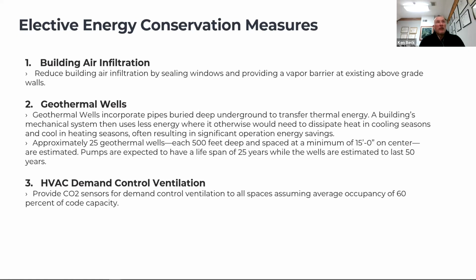So if you have spaces that have limited occupancy or no occupancy, we can dial down the ventilation based on actual occupancy of the space. So you may be running 10% of ventilation for 2/3 of the day in a space when you don't need the 100%. So it's a very cost-effective way to save energy very quickly.